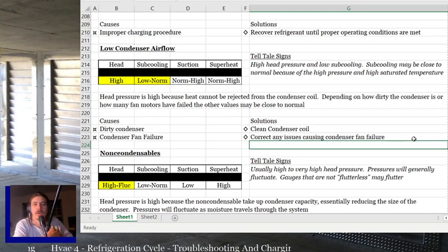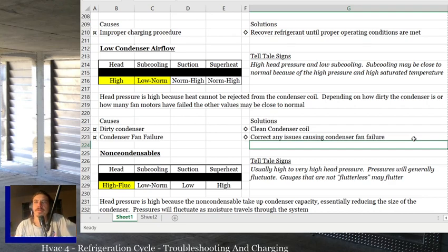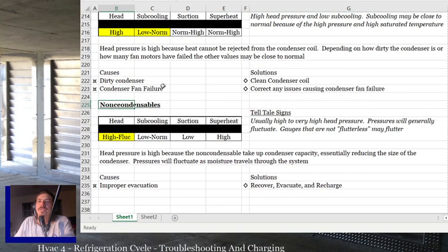If it's the only one, or it's just 1 out of 4 or whatever, the other values may be close to normal. Cause: a dirty condenser or fan failure. Clean the condenser coil, correct the condensing fan failure. That's pretty much what it boils down to, right? And then the last one we will talk about is non-condensables.